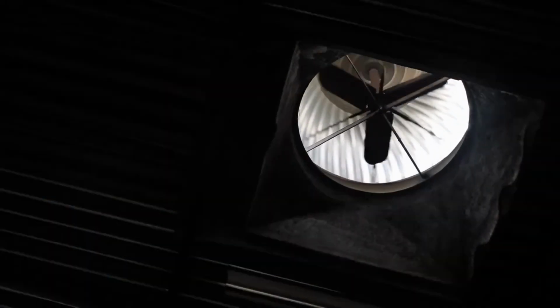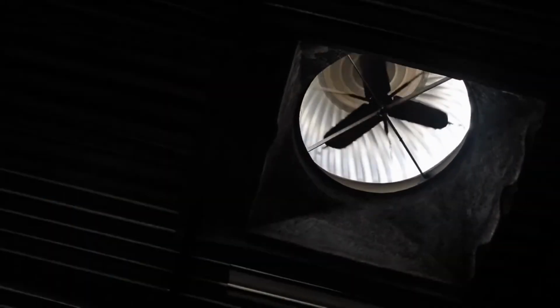We keep talking about cleaning a room. What does it mean if a room is clean? That's a good question. It's the number of turns of air. To create a fresh or safer environment, you want to cycle the air in a room as many times as you can through a filtration system, and you want to pump as many ions into the system to scrub the air and surfaces. They're recommending about 8 turns of air an hour in a room. If you can turn the air 8 times in an hour through filters and provide ionization, you're providing an incredibly safe environment for people to be working in. So that means you're breathing all new air 8 times an hour.